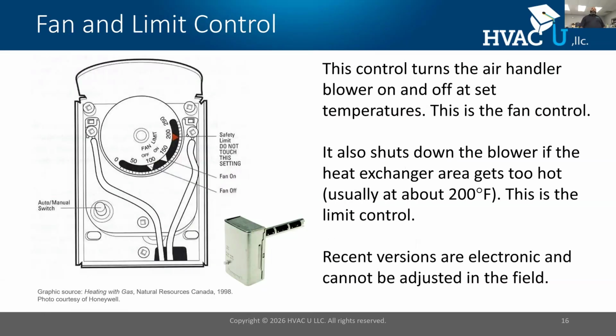This brings up our limit control, or fan limit control. On older systems, we had a fan limit control where this control handled the fan function on the furnace and the limit. Newer furnaces now have an integrated circuit board that controls the fan function, but they still have this limit. What does this limit do? Duct undersizing is so prevalent that manufacturers take action to protect the equipment from overheating. We call it a limit control. Typically it's set around 200 degrees Fahrenheit or so, depending on the manufacturer. If I can't circulate enough airflow to keep that bonnet cool, this limit shuts the equipment off. So this is the limit control.